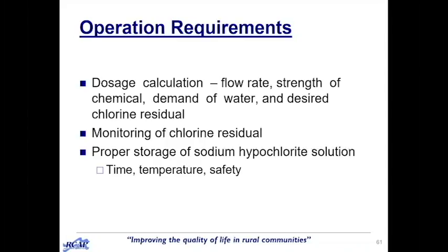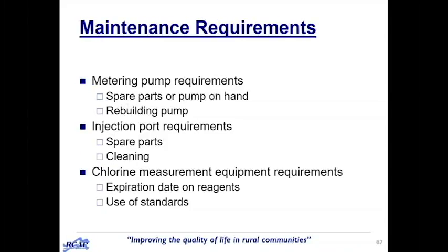You're also going to have to monitor the chlorine residual. So this is an important thing to point out to folks in this training, that that's one of the things they're going to have to do, and that if you're going to be storing the sodium hypochlorite, there are certain things you need to take into consideration, such as how long you keep it, what temperature it's stored at, and how you store it safely. So these are all important factors for people to consider when they are looking at this particular technology.